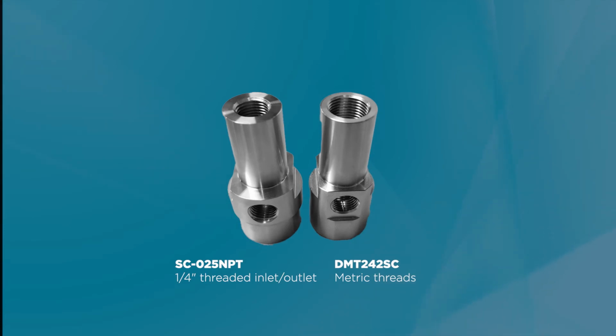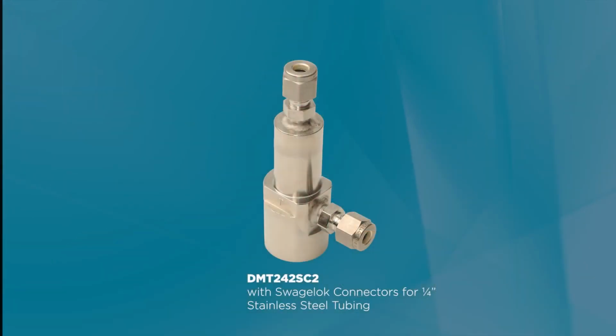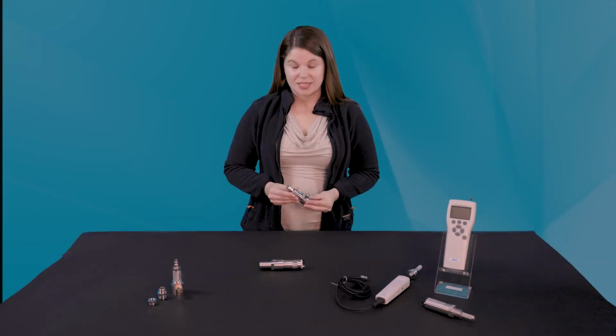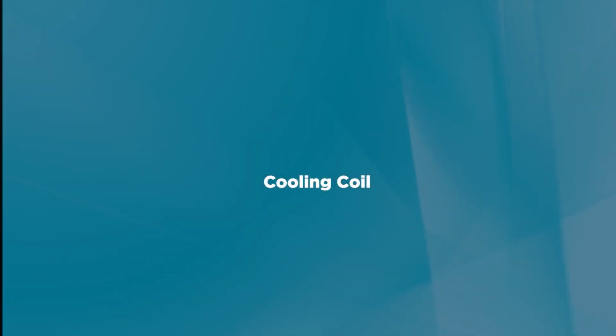In addition to the DMT242SC, we also offer the DMT242SC2, which has Swagelok connectors for 1/4-inch piping for the inlet and outlet. This is easy to pair with our cooling coil. The primary application for the cooling coil is to allow for gas to cool enough to be safely measured. Almost all of our dew point probes have an operating temperature between 60 and 80 degrees C, so if the gas temperature is above that, it will need to cool before reaching the sensor.